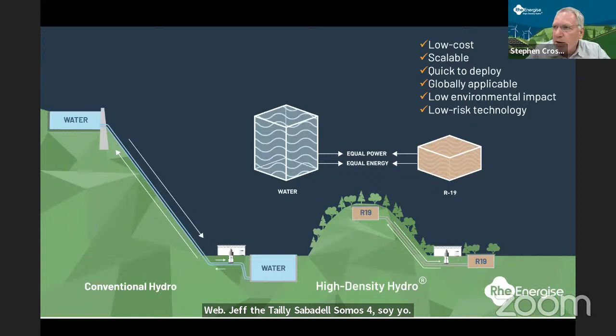So our solution, we call it high-density hydro, is based on traditional pumped hydropower. For anyone who doesn't know, that's where you have a reservoir behind a dam at the top of a mountain, and another reservoir at the bottom. When energy is abundant, you pump it up, and when energy is scarce, you release the same water down through a pipe and regenerate electricity via a turbine. Round-trip efficiencies for traditional pump storage can be a little over 80%, with figures typically 75 to a little over 80%.